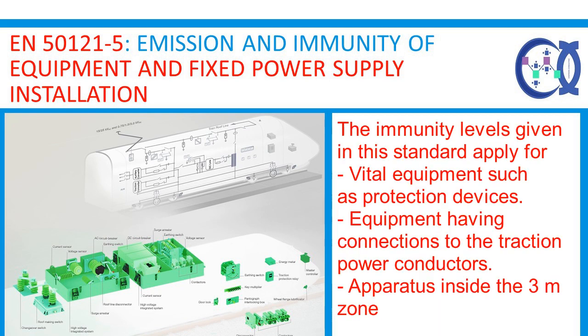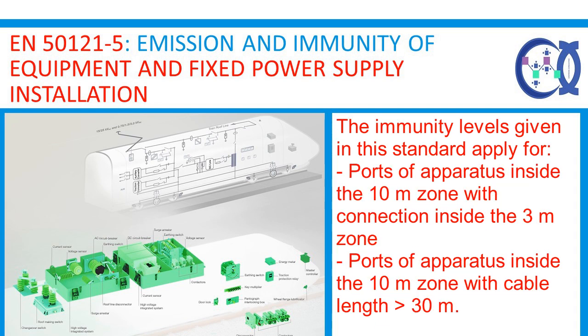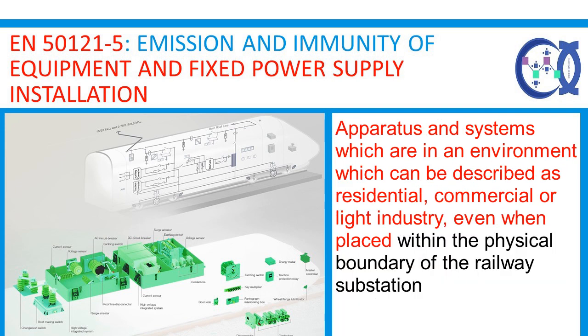The immunity levels given in this standard apply for: vital equipment such as protection devices; equipment having connections to the traction power conductors; apparatus inside the 3m zone; ports of apparatus inside the 10m zone with connection inside the 3m zone; ports of apparatus inside the 10m zone with cable length greater than 30m; and apparatus and systems in an environment which can be described as residential, commercial or light industry, even when placed within the physical boundary of the railway substation — ports of apparatus inside the 3m zone.